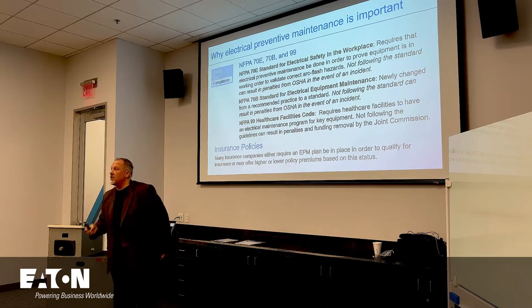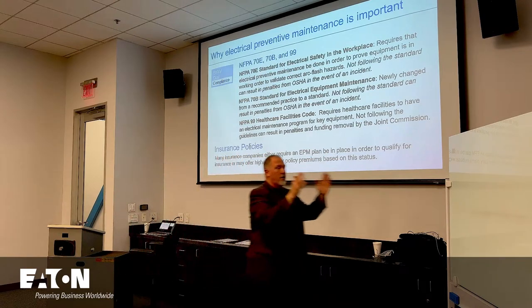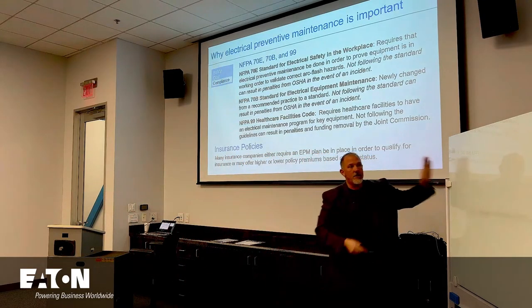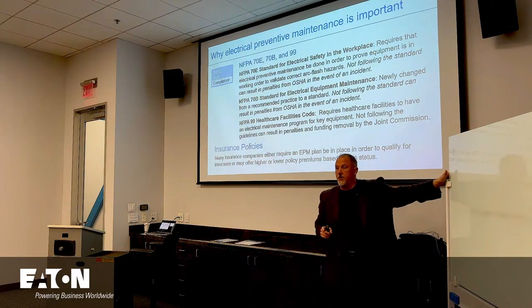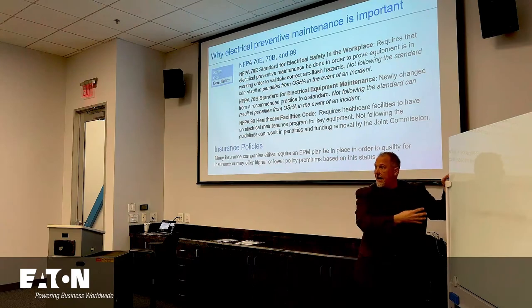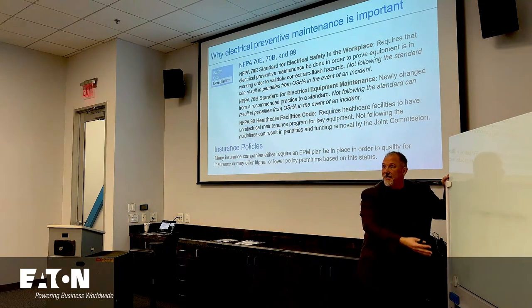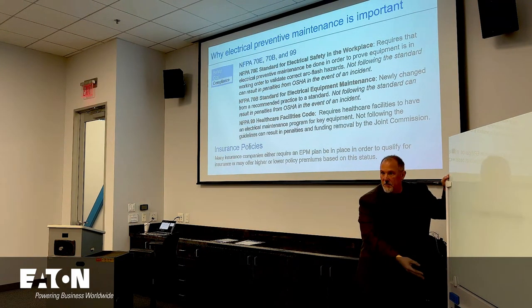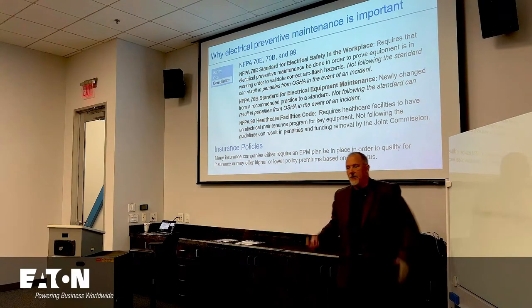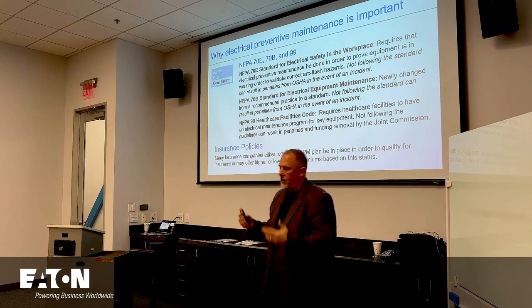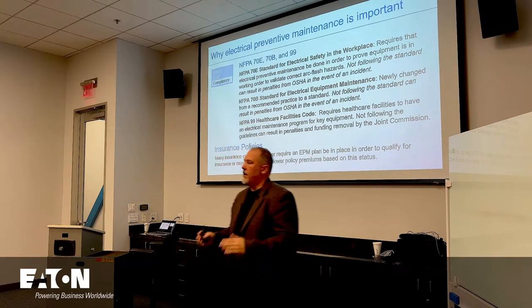The electrical worker has to walk into it. If the electrical worker is going to work on this piece of equipment, they have to look and ascertain the condition of maintenance. That's a 70E requirement. And if I can't demonstrate how to determine the condition of maintenance and whether it was maintained, then your safety plan is on sand, not on a good foundation.